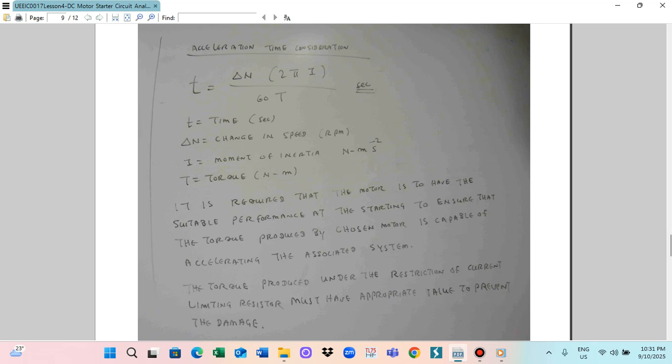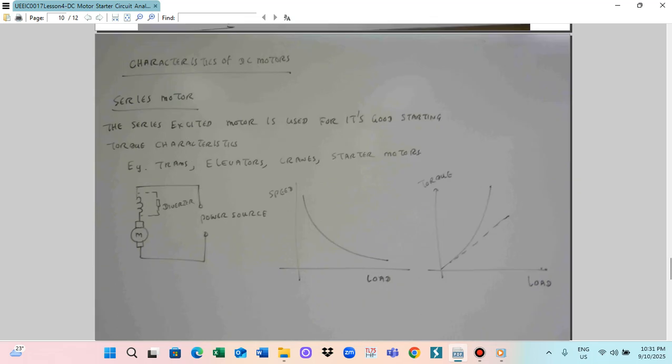So this means that when the motor accelerates, torque is produced, and the motor has to withstand this torque. This torque can damage the motor, so the motor has to have the appropriate structure and resistance to withstand it. So this is important. In this case, to limit this torque, we have to utilize the appropriate resistor. This appropriate acceleration resistor, dynamic resistor, has to be selected so that the torque will not be so large as to damage the motor.